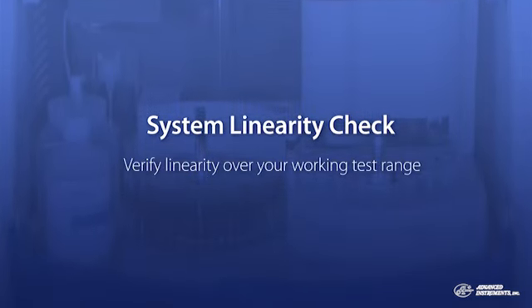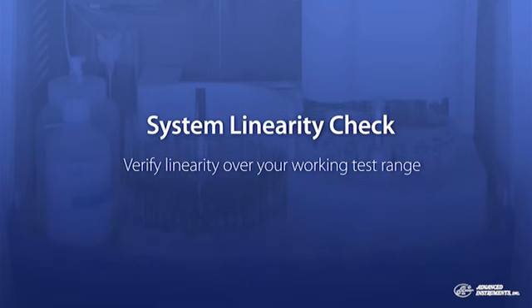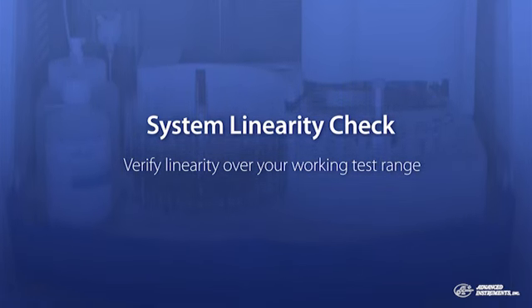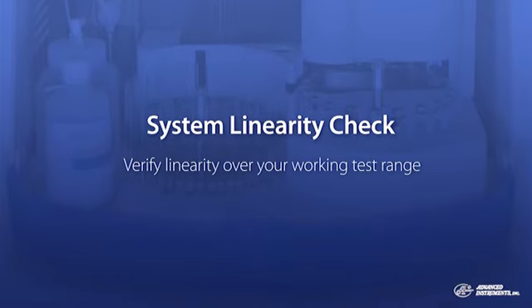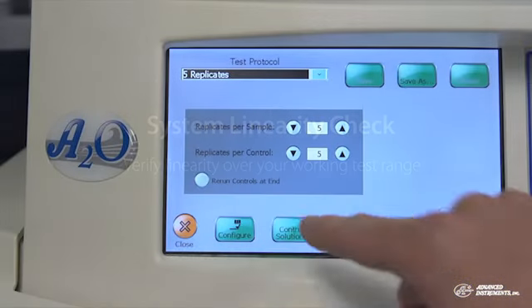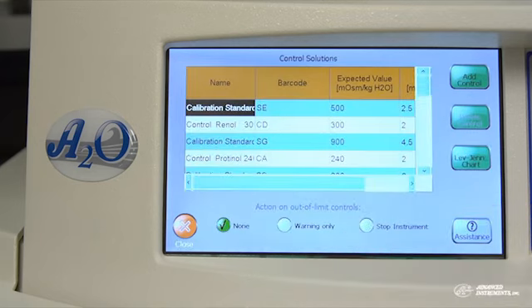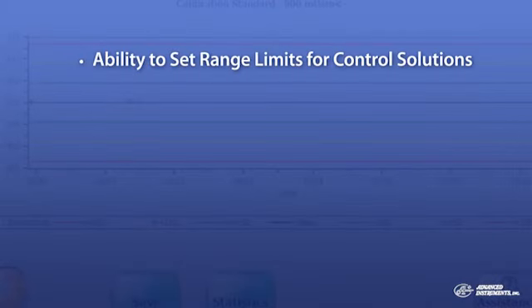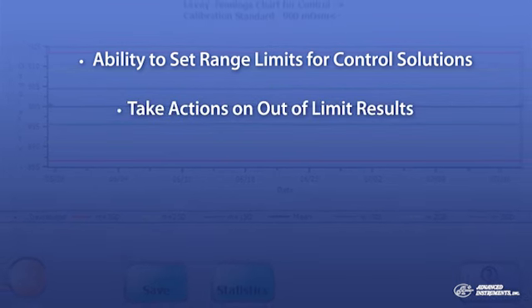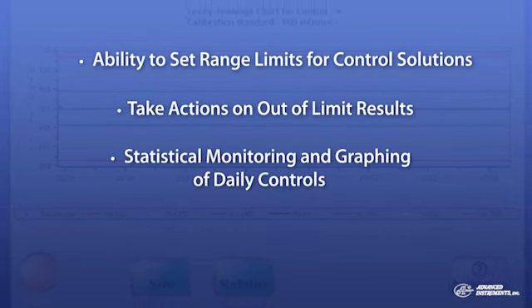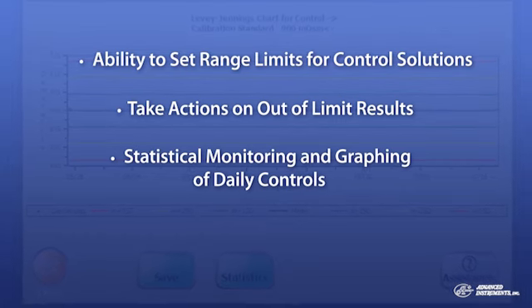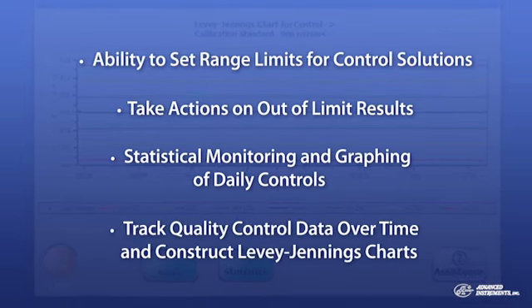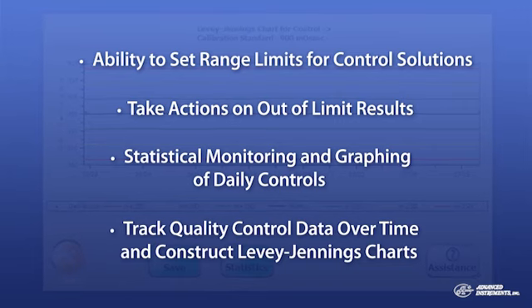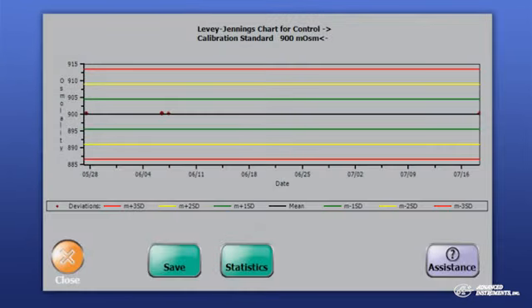The A2O features a built-in system linearity check with statistical reporting capabilities, making it easy to verify linearity over your working test range. Other enabling quality control features of the A2O include the ability to set range limits for control solutions and to take certain actions when control limits are exceeded, statistical monitoring and graphing of daily controls, the ability to track quality control data over time, and construct Levey-Jennings charts.